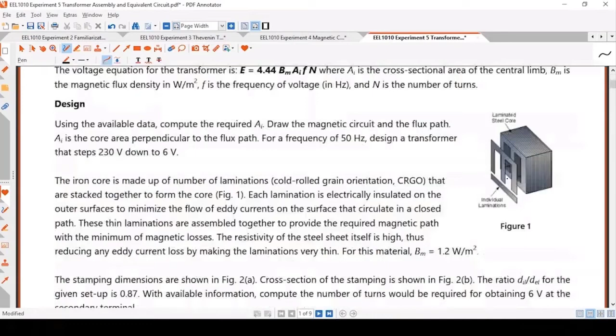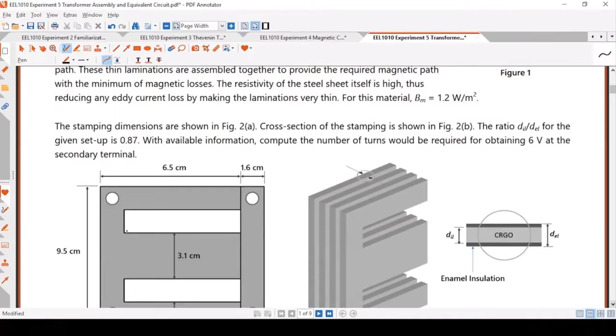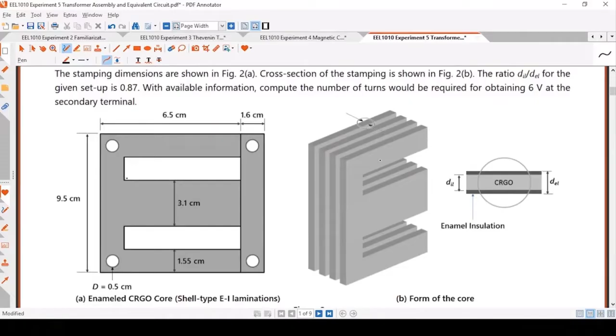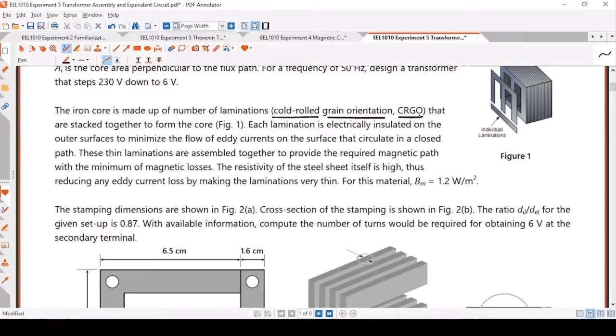We studied the core, which was independently made of stampings with an E section and an I section. Each of these sections is laminated with thin laminations made of cold rolled grain oriented steel, CRGO, meaning they are rolled in a particular orientation to have enhanced magnetic properties in that direction.